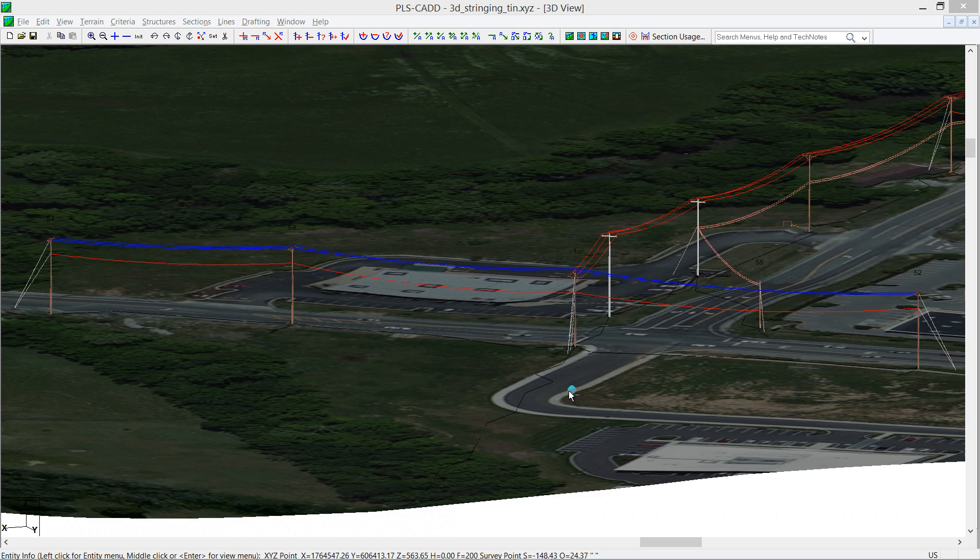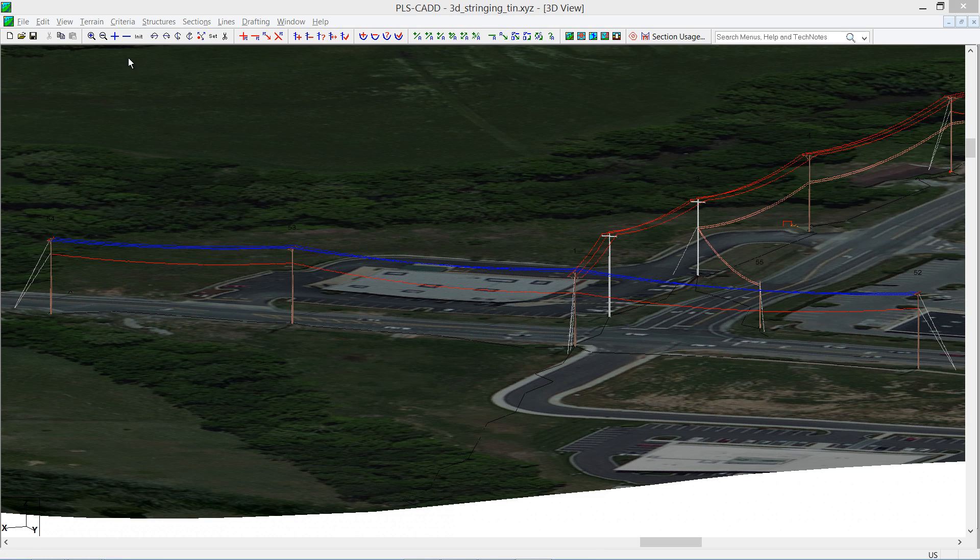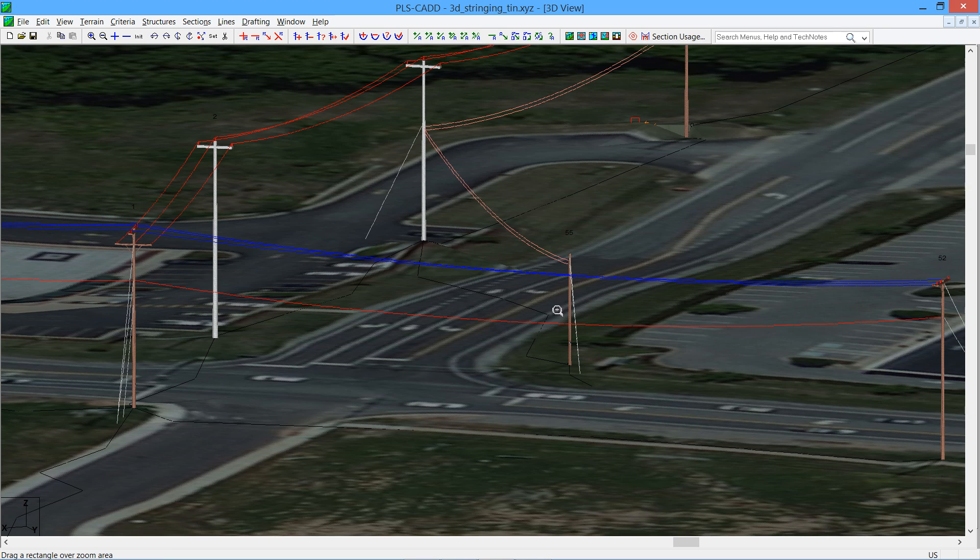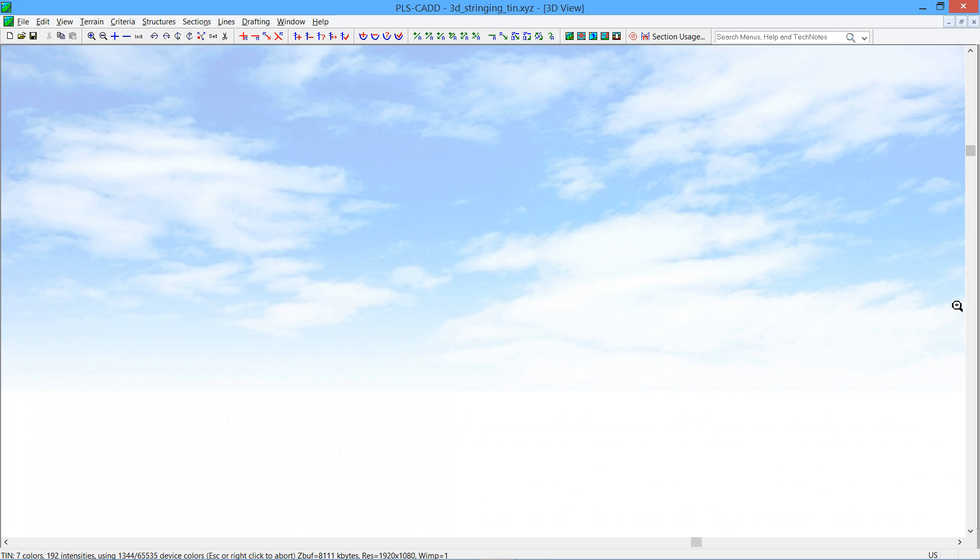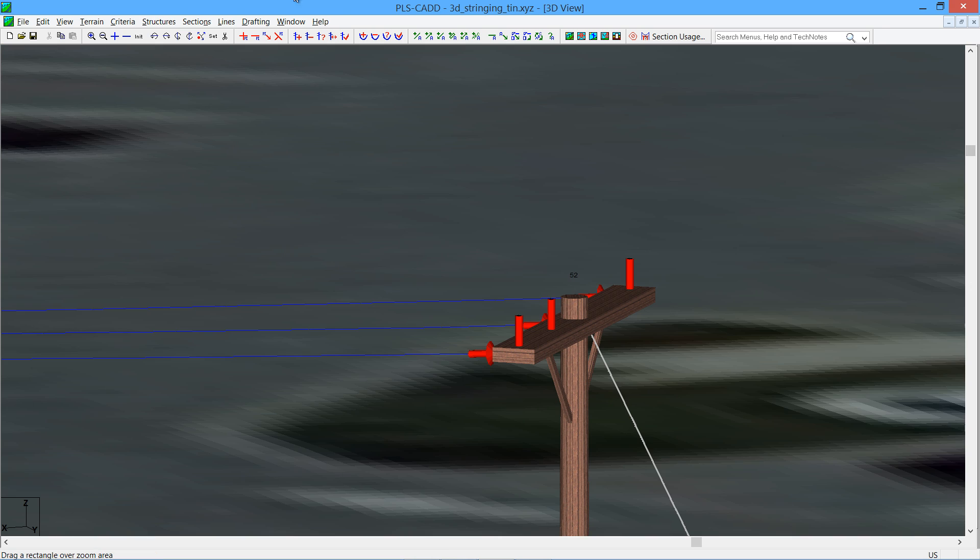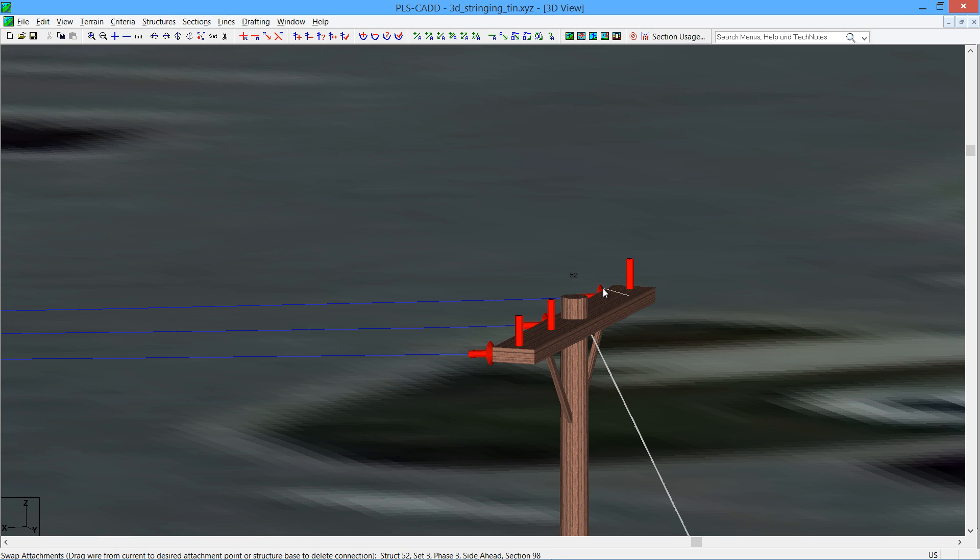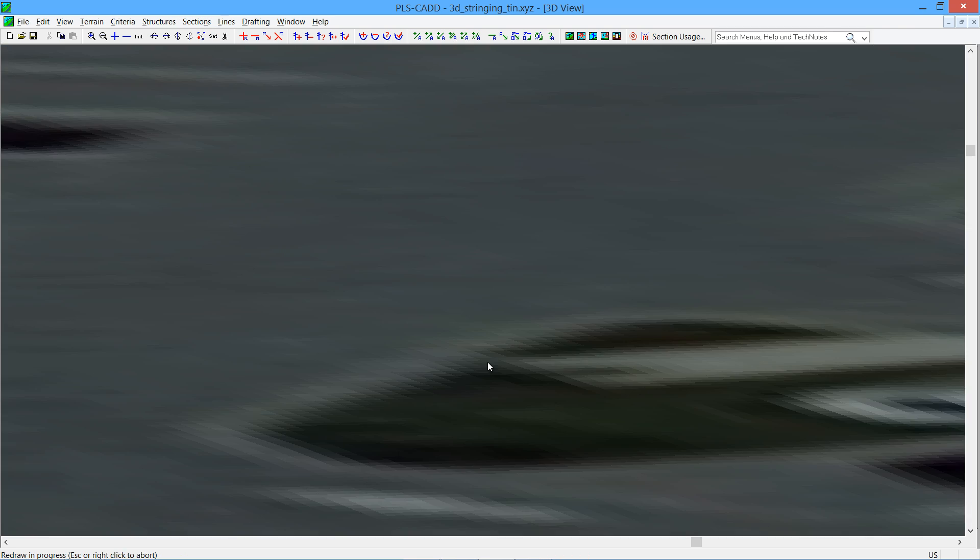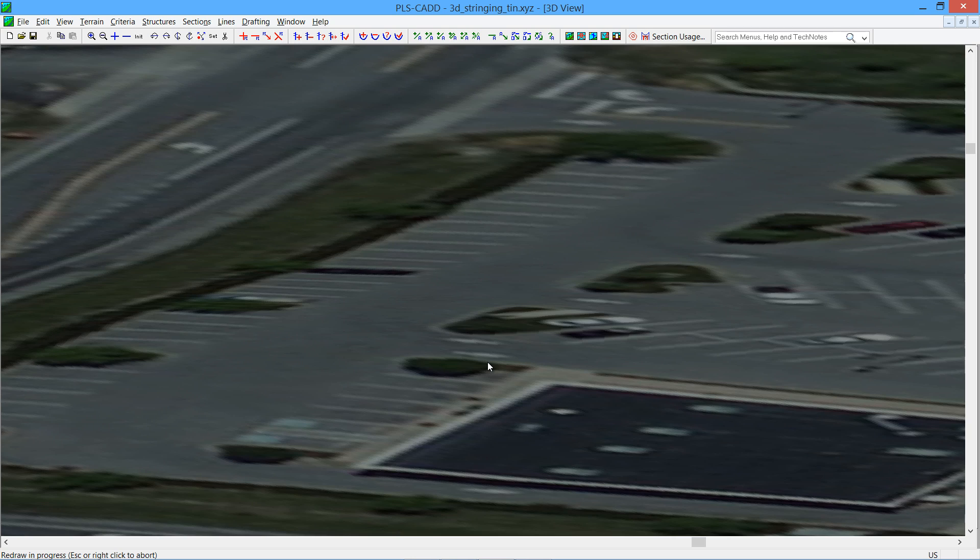Once you've got your wires strung, you may want to make some modifications. For example, I can see that between these two spans here my wires are crossing. So I would like to fix that crossing of phases right there. So I'm going to go to the right structure and I'm going to do a sections swap attachments. And I'm going to grab that insulator and swap it with the one on the near side. And that will swap out the insulators. And now you will see that the phases are not rolled through that span.